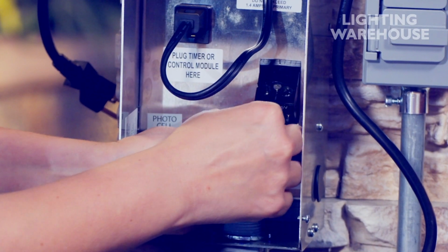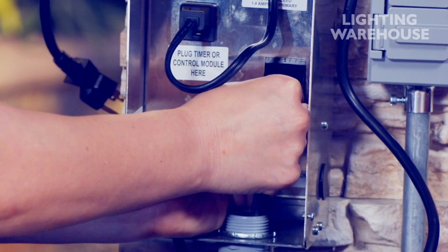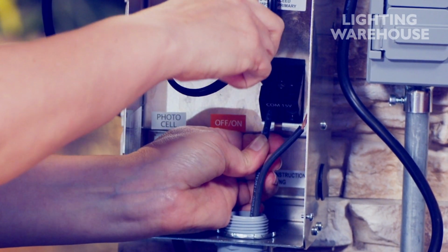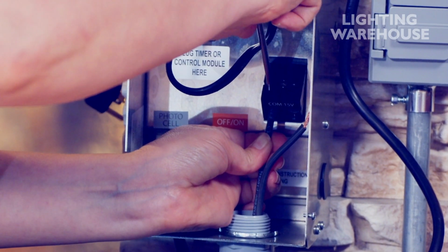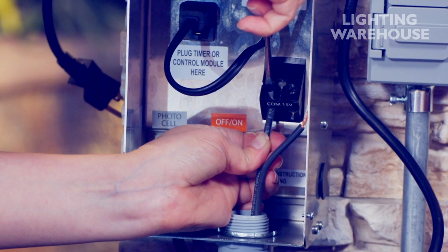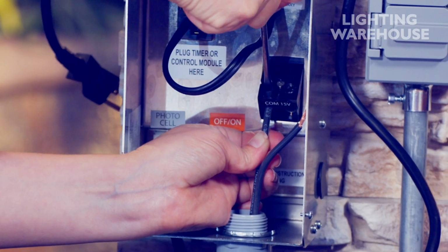So connect the wire with the writing on it to the COM or common, and the other will go to a terminal marked with a voltage number. Likely it will be between 12 and 15 volts, though you may have multiple options. Any should do. But if your run is on the longer side, go with 14 or 15 volts.